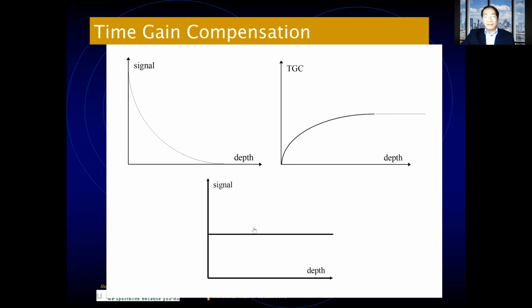that we will have a pretty much uniform homogeneous wave that is detected by the transducer and then worked on by the CPU. And so if you do not have this time gain compensation, you will see that closest to the probe, it's very, very clear, it's very, very visible, but farthest from the probe, it's going to be very dark, and maybe the resolution is not going to be very good.